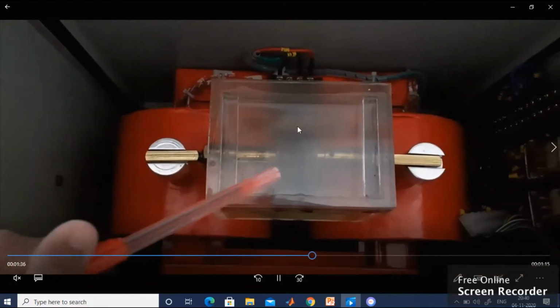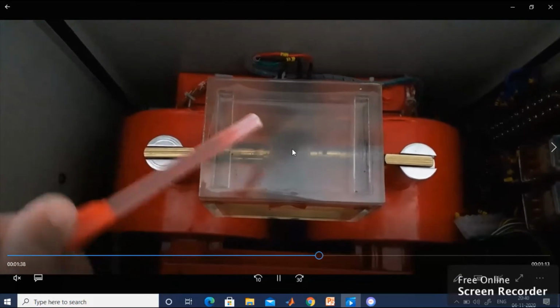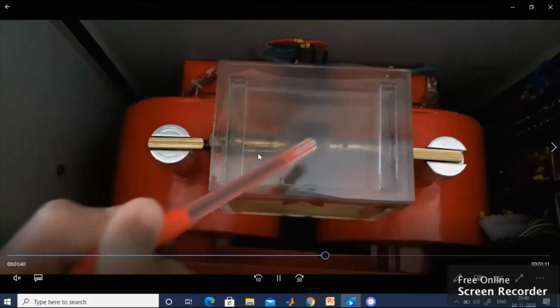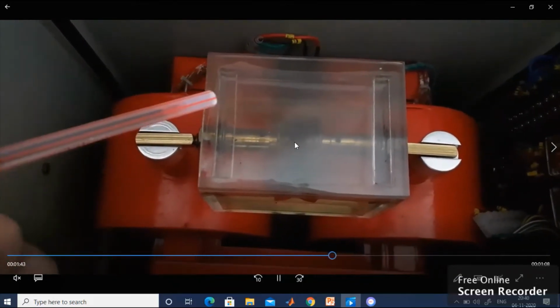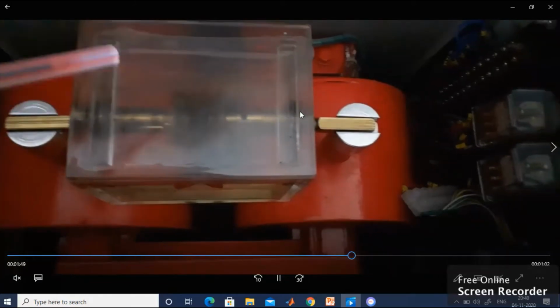You can have a brief observation inside. You have to observe very carefully. So transformer oil has been kept inside the beaker. In between, the electrode gap arrangement is available, so the gap is approximately 2.5 mm. No need to set the particular gap, it's already there, already maintained at 2.5 mm.